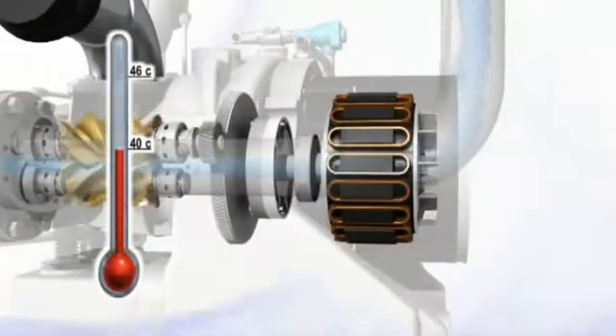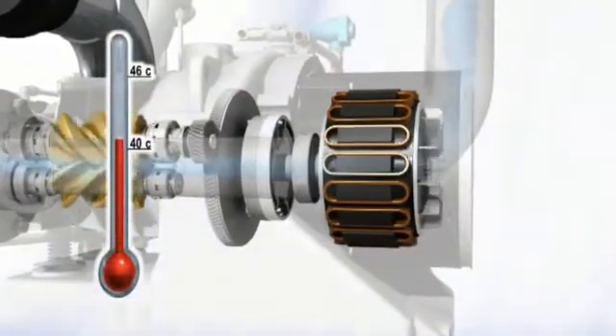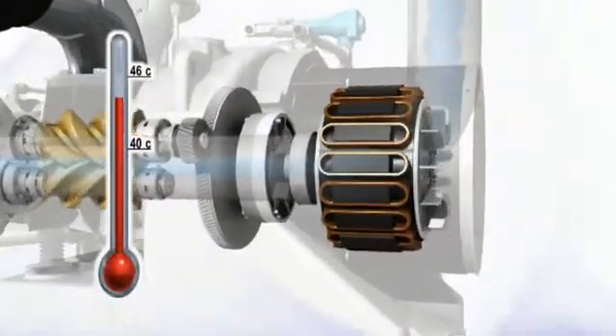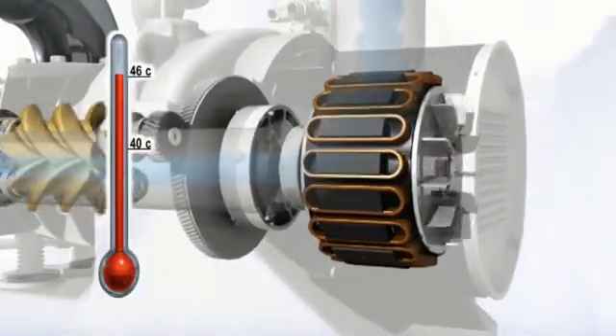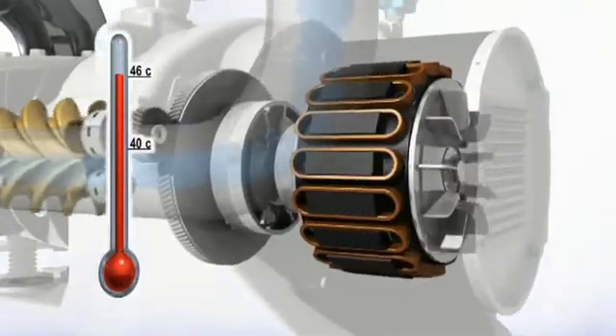Unlike standard motors and frequency drives which are rated at 40 degrees Celsius, the Nirvana HPM motor and matching drive are conservatively rated to operate continuously in temperatures of up to 46 degrees.